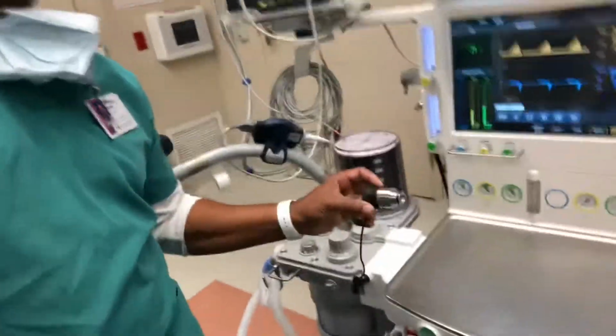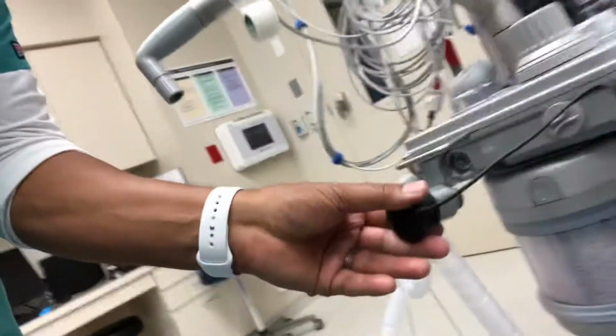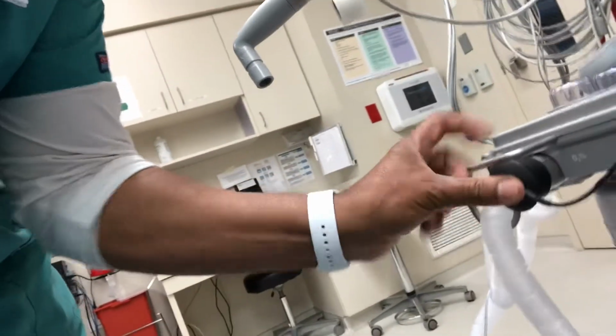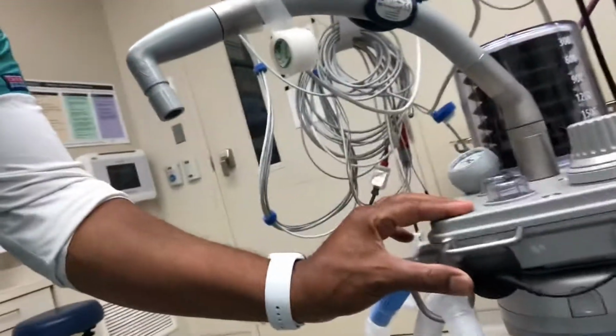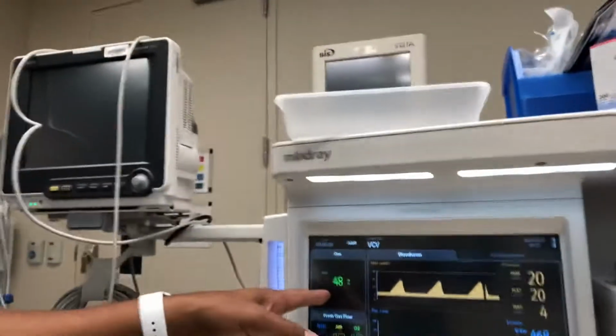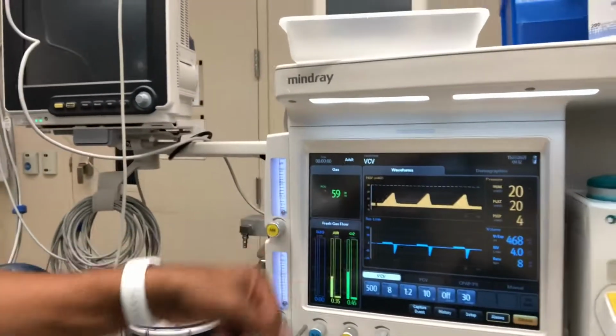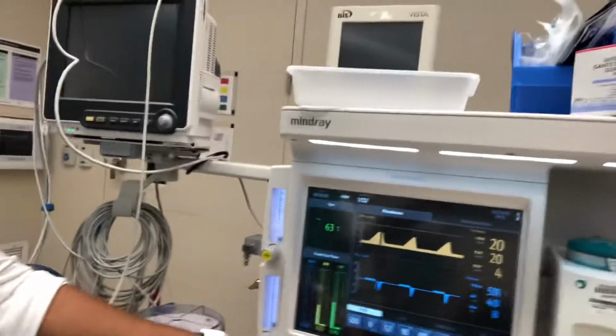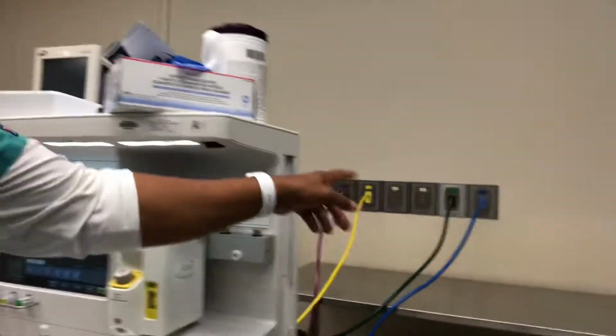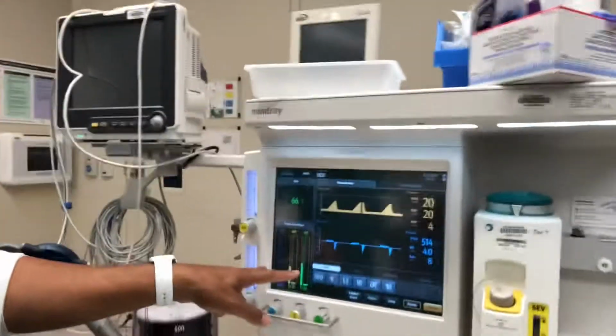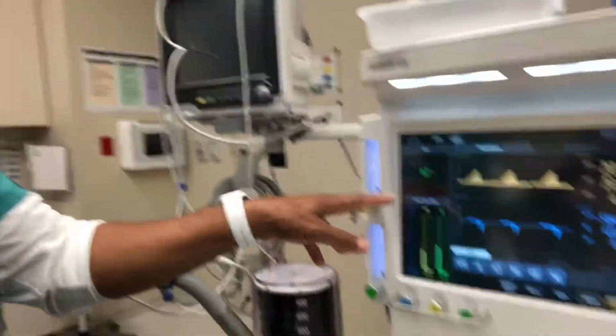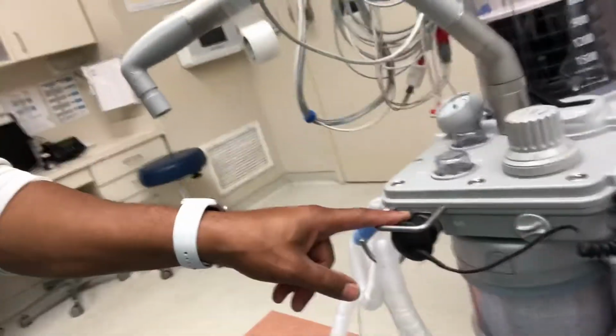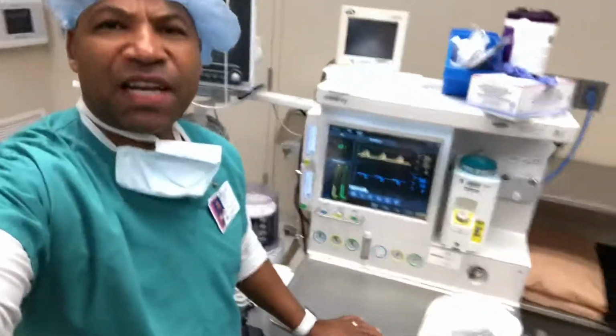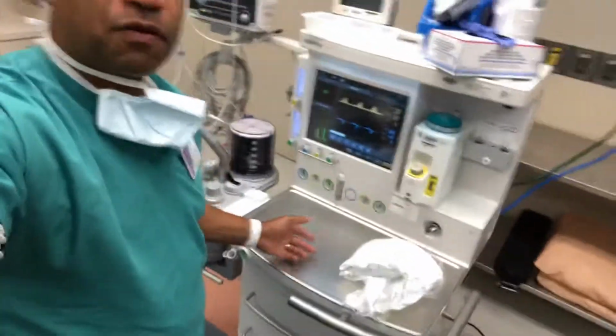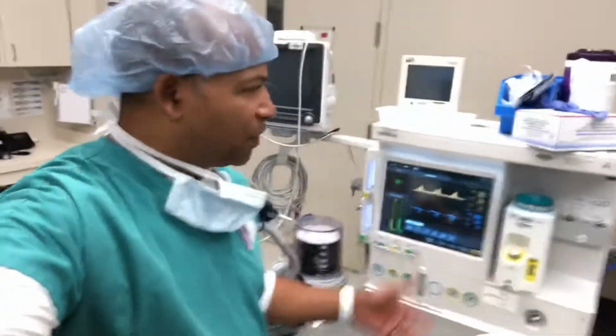What I'm going to do now is put back my oxygen sensor, and this connects right back in here. That's for your oxygen percent. Put that back in there, and that's going to start to increase my FiO2 that I have set, which is our oxygen, and of course our green line, which is our oxygen on the wall. So we see that climbing, we see our oxygen sensors working, and if you have a problem, you will replace your oxygen sensor over here, or try to calibrate it first. I always try to follow the calibration procedure because I think it's just a lot better. But anyway, I hope these quick tips have helped you a little bit in familiarizing yourself more with the Mindray units.